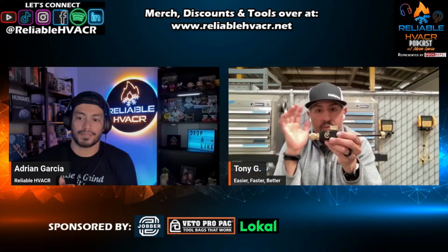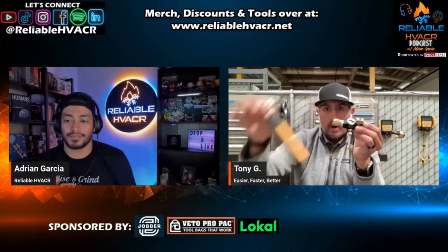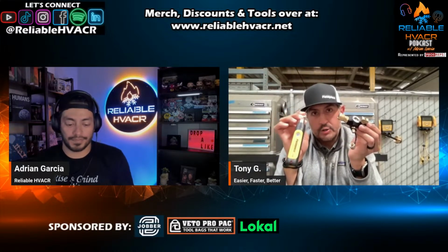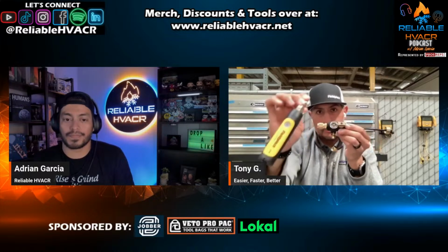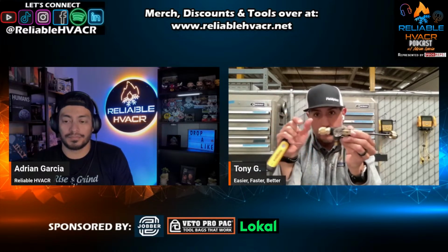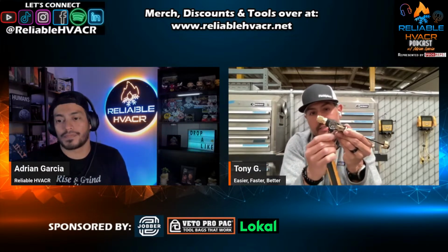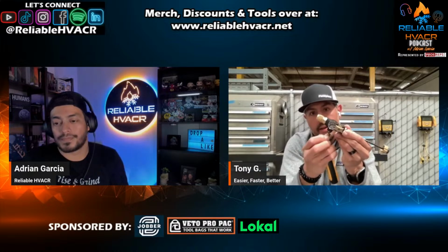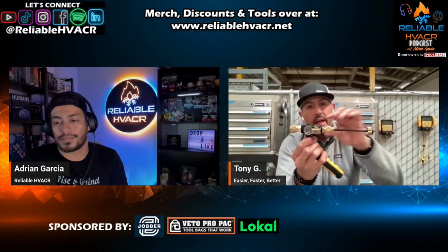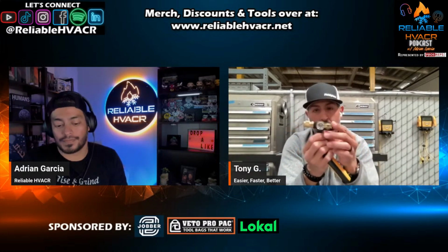Actually, even before we get to that, wireless probe, right? One of the biggest questions when this came out is, well, how do I charge the system with refrigerant if I'm using one of these, right? And a real easy way, and the best way, is to have your valve core removal tool, screw it onto the system, and then you screw your pressure probe onto the side port of your valve core removal tool, right? So now you have the ability to measure the pressures in your system, and then you have your hose to screw onto here, and you can charge and you can recover with refrigerant.